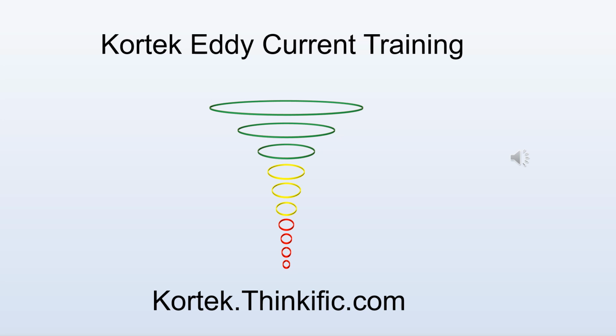Any eddy current testing system requires the following basic components: a generator or an oscillator to generate the alternating current supplied to the test coil, a test coil, and an indicating device, such as a meter or an oscilloscope. Many eddy current instruments are standalone, meaning they have their own display and require no other equipment to perform the test, other than the test coil.